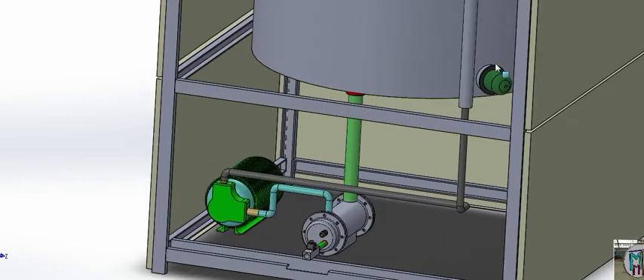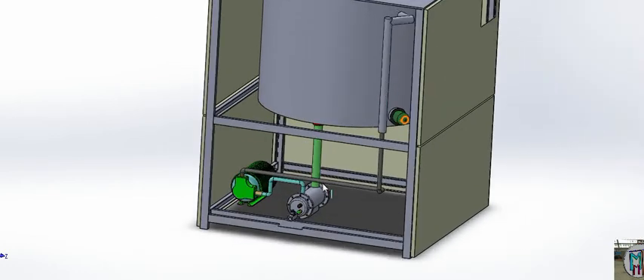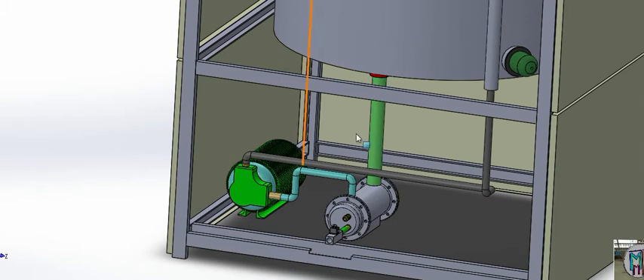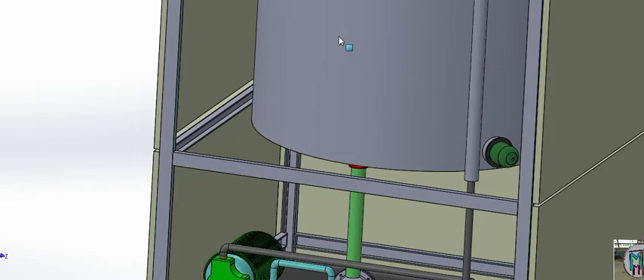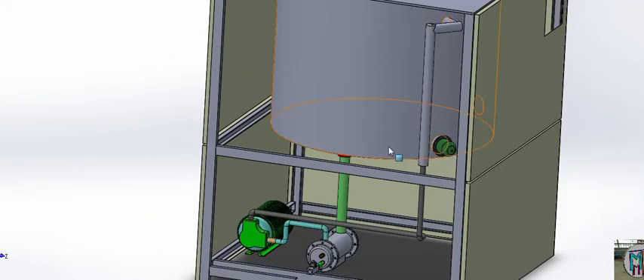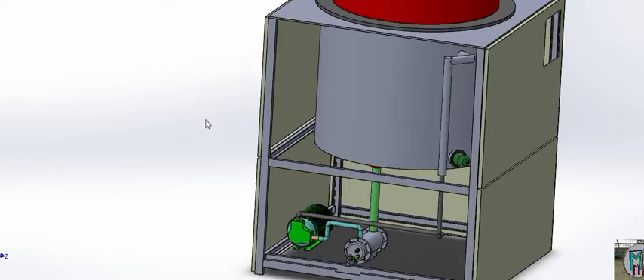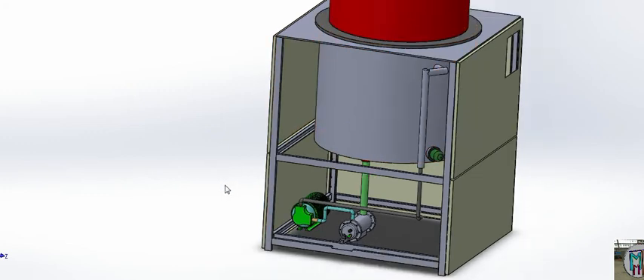Suppose the heater is working well, but the pump is not circulating your thermic oil. In that case, the heat will be only on the bottom side, not the upper side. So we will fix one sensor or thermocouple at the middle side. When the pump rotates, your thermic oil will be in circulation, so your temperature will be uniform all over your tank. So what is the working of this?